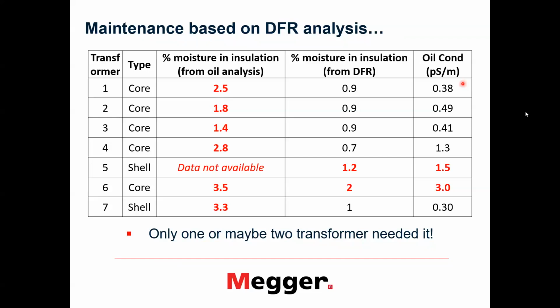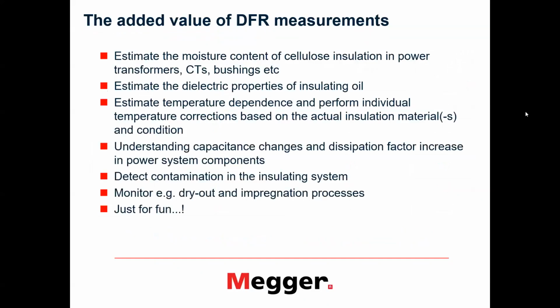And also dielectric frequency response analysis is very non-invasive. You don't need to open anything. You cannot contaminate anything, and you can make a measurement today or tomorrow, at different temperatures, and see how results are. Basically, I would recommend it as a tool for moisture assessment, or a tool for transformer diagnostics. Besides estimating moisture content, we can have an estimation of dielectric properties of oil. We can see the temperature dependence and perform individual corrections so that it's more accurate than tables, and so on.